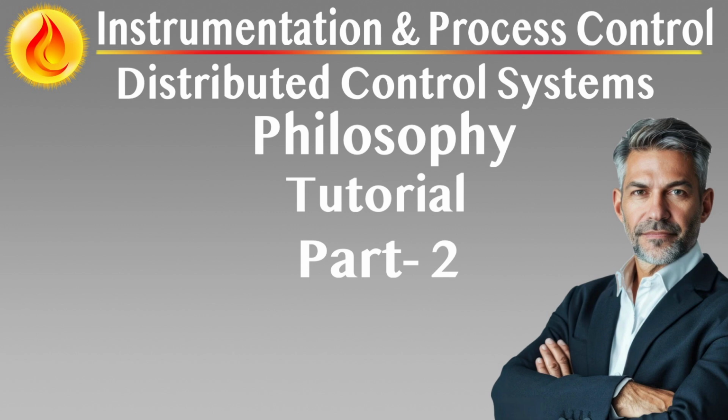Digital cause and effect matrix implementation. All shutdown logic is derived from a digital cause and effect matrix validated during HAZOP and SIL assessment. Any logic or I/O changes automatically update the matrix for traceability and audit compliance.